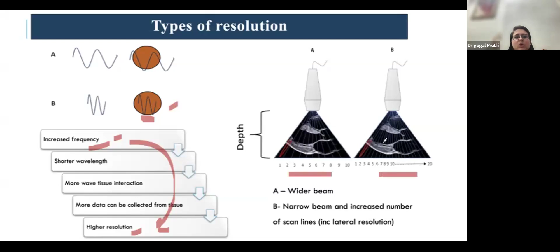So next is lateral resolution. In lateral resolution, you can see, for example, in figure A, you have 10 scan lines. These are hypothetical scan lines, and figure B has 20 scan lines. So if you have increased scan lines per frame and focusing, it improves your lateral resolution. Now you have to understand what is frame and frame rate. Each image created by a sector scan is known as a frame, whereas the frequency at which the sector is rescanned is known as the frame rate.